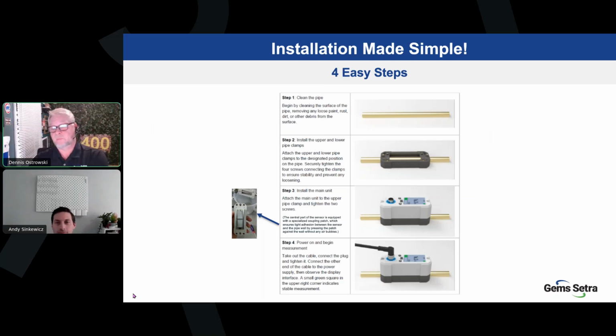Okay, here's a 4-picture diagram of the simplicity of mounting this device. You've got a clean pipe, you've got an upper and lower pipe clamp, which is 4 screws. You've got 2 screws to mount the device, and then you've got your M12 connector for your 4 to 20 milliamp output. It really is that easy. You see a little image to the left there. That is underneath the device. There are contact pads that are required. They come already inserted into the device, but if they're ever damaged or missing, they can be ordered separately. Clamps as well can be ordered separately. Okay, next slide.